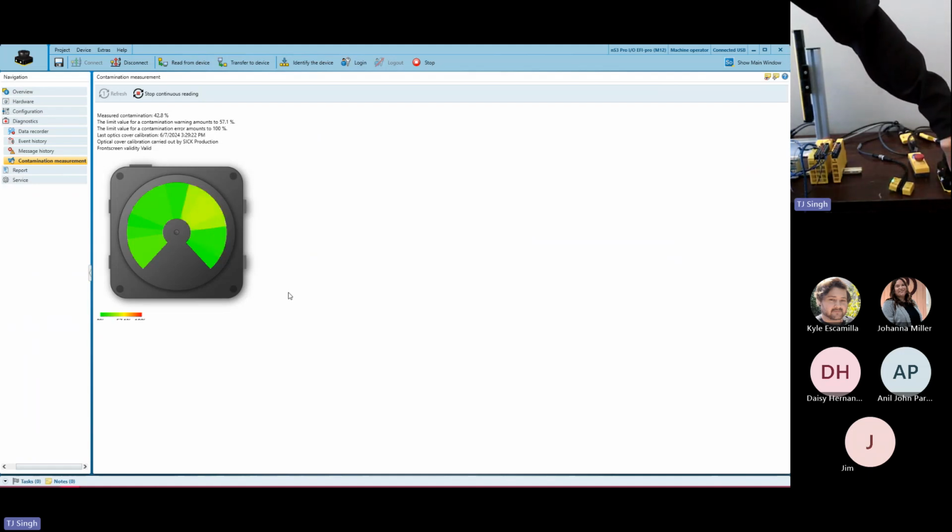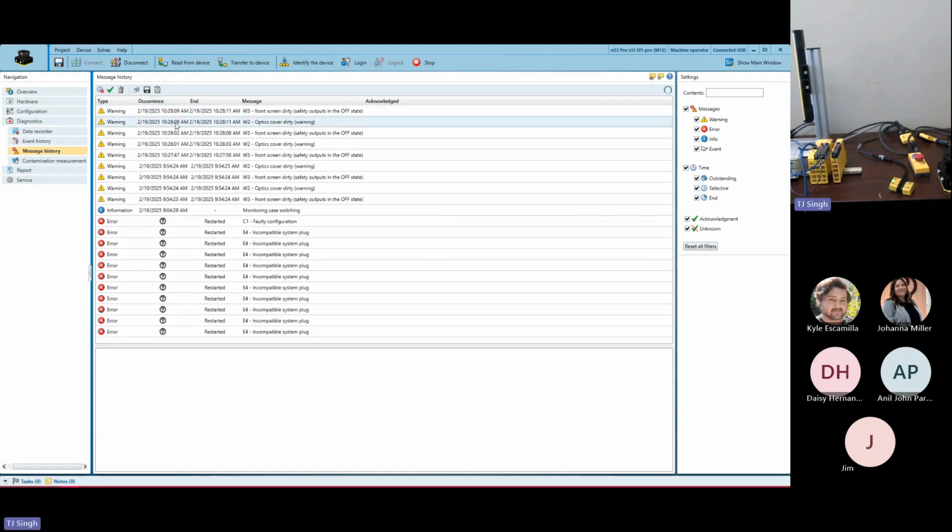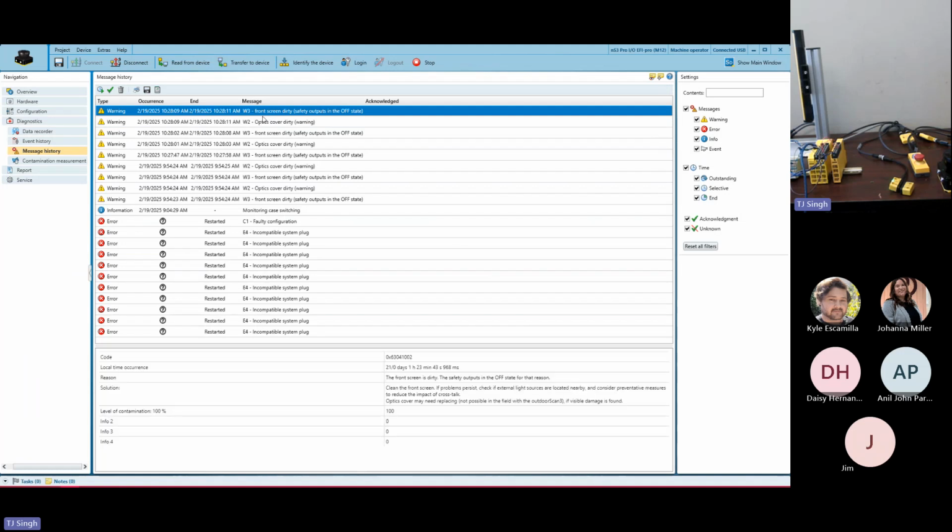Now if I press gently against it, you will see it's not dark red or whatever. It's like yellow, orangish kind of. And that just tells you that it's still pretty smart, where it knows that I'm only going to trigger an output for a contamination when there's an actual system error. And these things also repopulate. So you just saw it updated. Right now is what, 1028. Oh, we're getting close. So it told you, okay, front screen dirty, and then better clean it up, right?